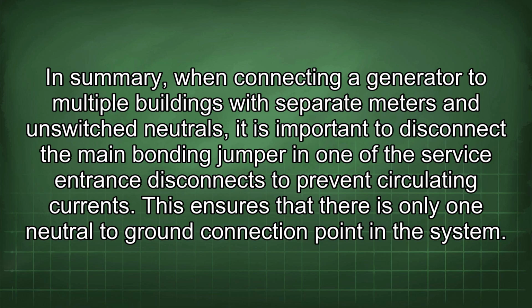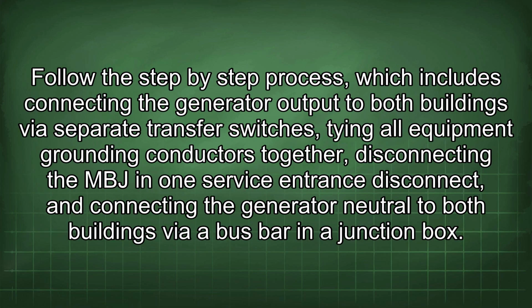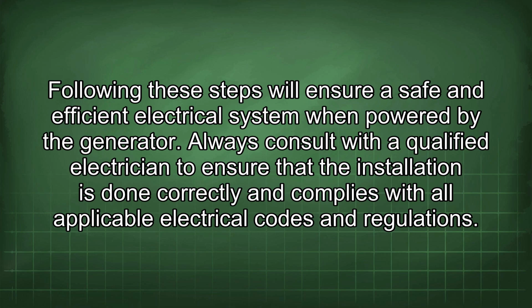In summary, when connecting a generator to multiple buildings with separate meters and unswitched neutrals, it is important to disconnect the main bonding jumper in one of the service entrance disconnects to prevent circulating currents. This ensures that there is only one neutral to ground connection point in the system. Follow the step-by-step process, which includes connecting the generator output to both buildings via separate transfer switches, tying all equipment grounding conductors together, disconnecting the MBJ in one service entrance disconnect, and connecting the generator neutral to both buildings via a bus bar in a junction box. Following these steps will ensure a safe and efficient electrical system when powered by the generator.